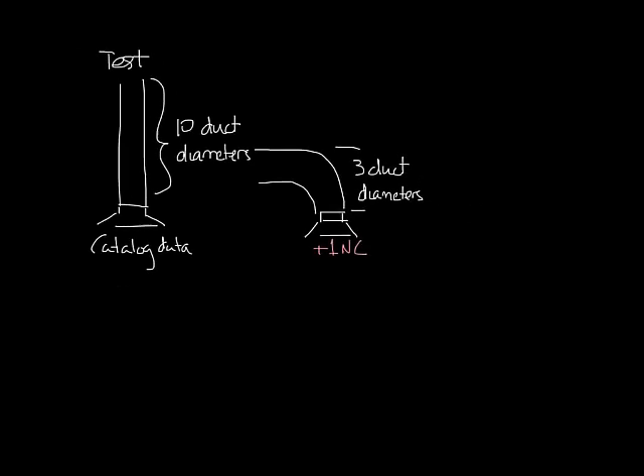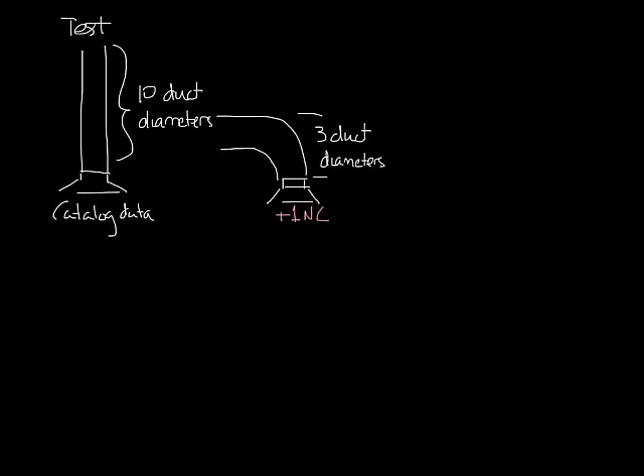Okay, let's scoot this over a little bit so I have more room. The next best condition is if you can get a soft bend of flex duct going into the top of the diffuser. This will be about 1 NC louder than catalog data.